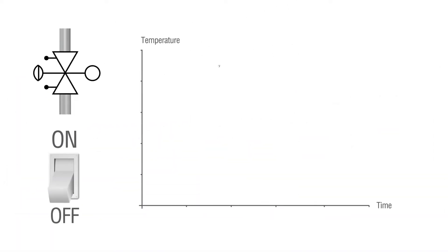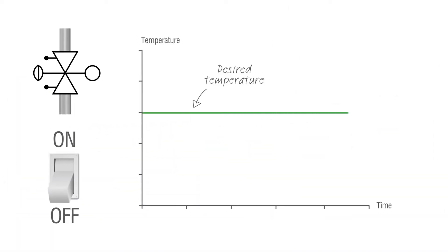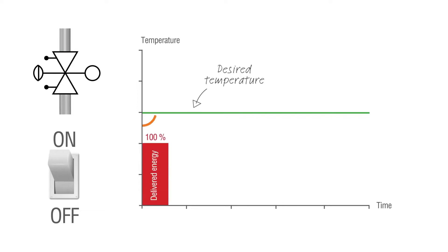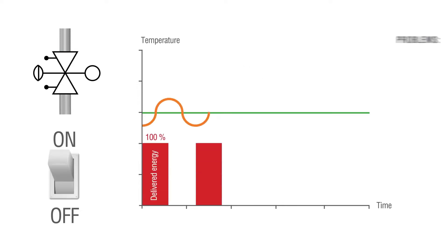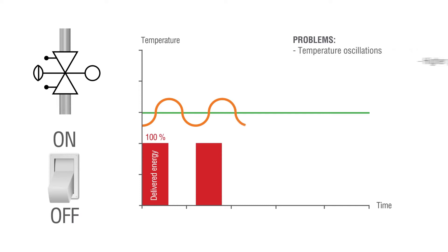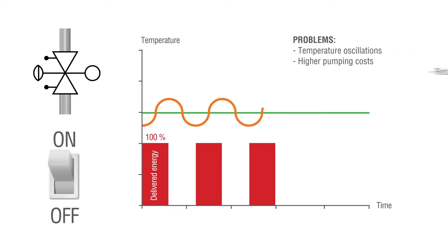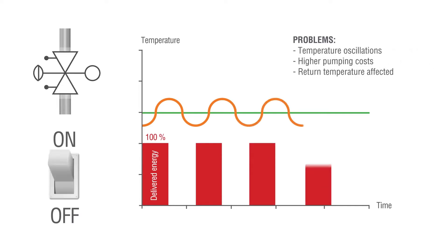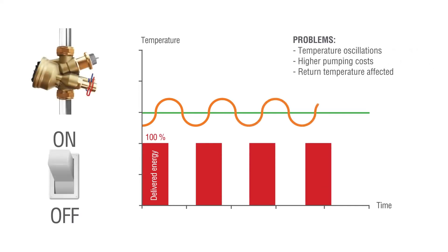If you use on-off control, the valve is either fully open and delivers 100% flow or fully shut. This leads to temperature oscillations and higher pumping costs. The return temperature is also affected.